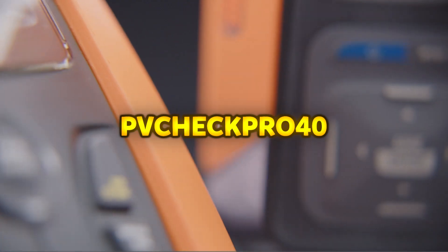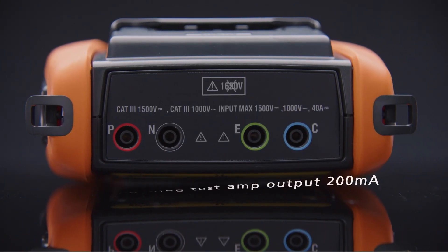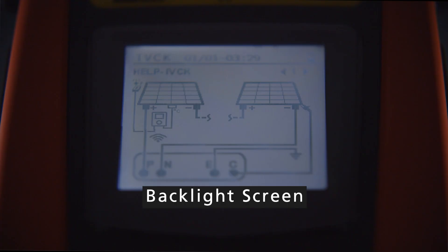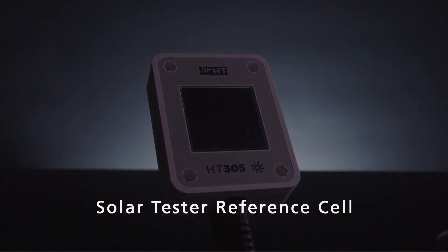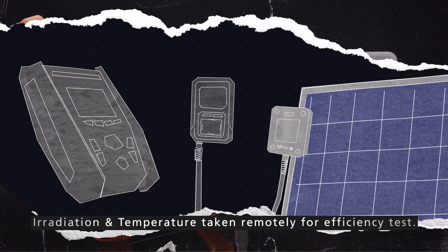PVCheckPro40. The PVCheckPro40 is a commissioning tester designed for comprehensive safety measurements and verifications of photovoltaic installations in compliance with IEC-EN-62446 standards. It streamlines the commissioning process with a single GO key stroke, allowing rapid and efficient testing of PV systems. Equipped with seamless mode, the PVCheckPro40 can sequentially test all strings within a combiner box without manual intervention, improving workflow efficiency.